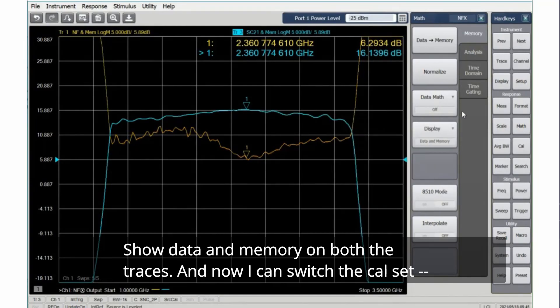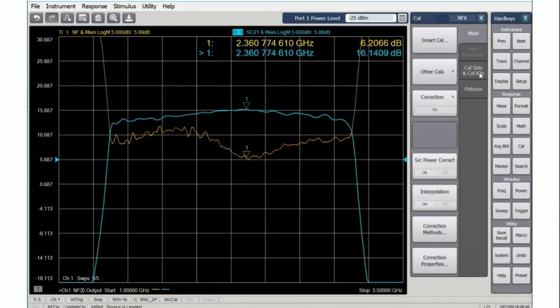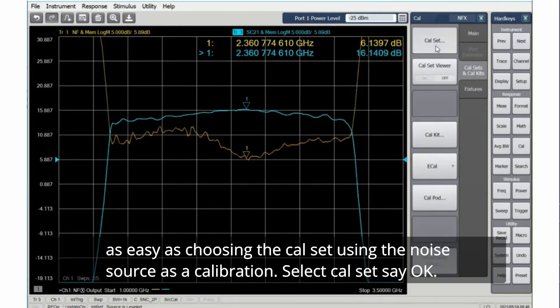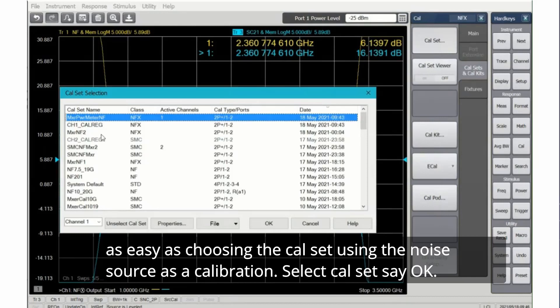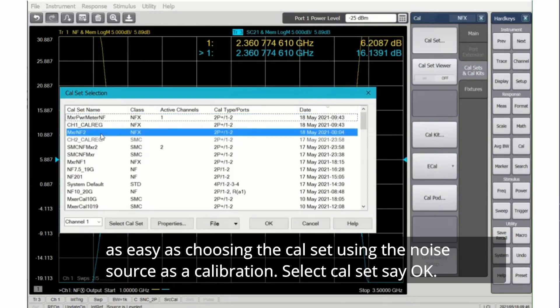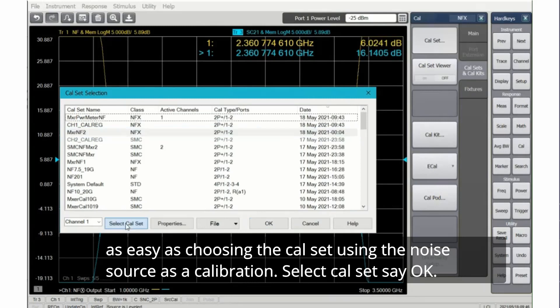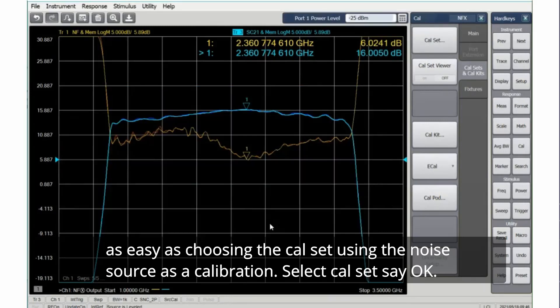And now I can switch the cal set as easy as choosing the cal set using the noise source as a calibration. Select cal set, say OK.